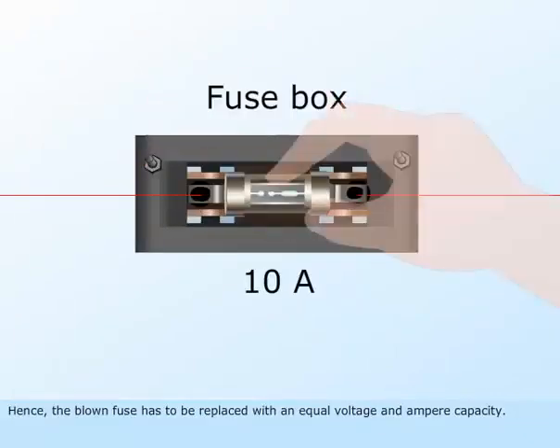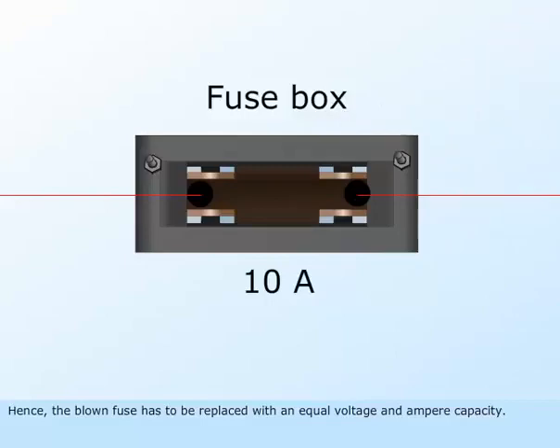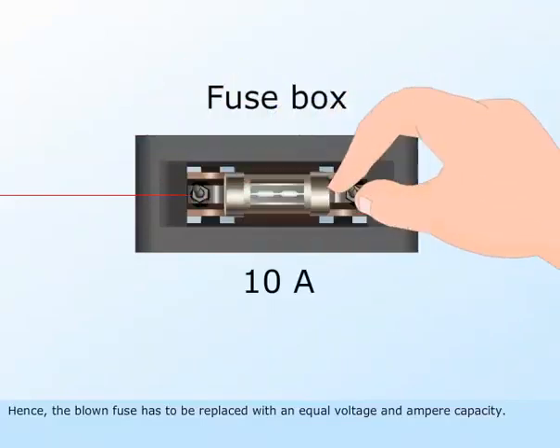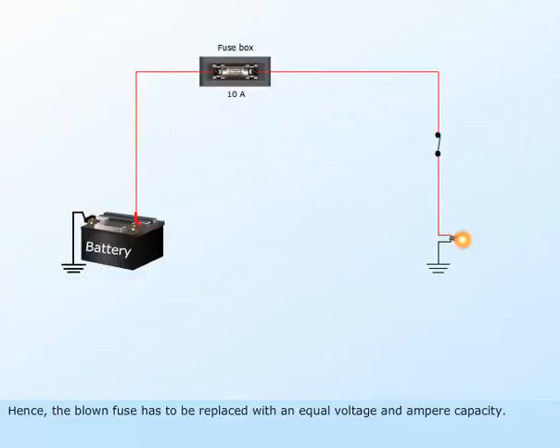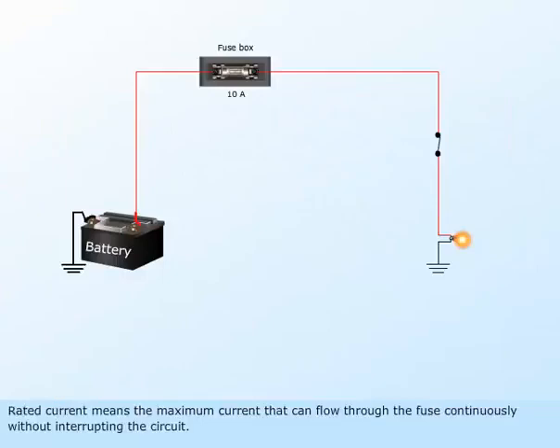Hence, the blown fuse has to be replaced with an equal voltage and ampere capacity. Rated current means the maximum current that can flow through the fuse continuously without interrupting the circuit.